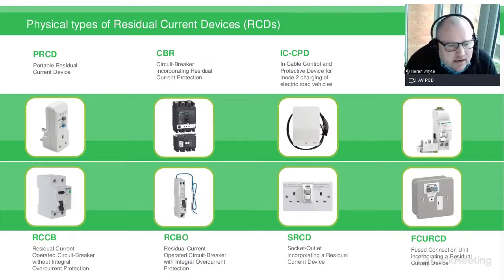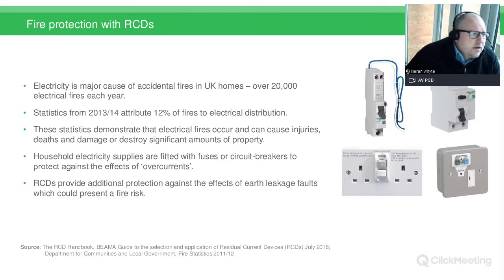They were probably seen in toilet areas, commercial and public toilet areas, where they used to feed the hand dryers, and they'd just be mounted at high level out of reach, which gives protection then to the cable and the circuit going down to the actual hand dryer itself. Not seen much these days. What we're seeing more is at point of source, the RCBO controlling the whole circuit, because there are very few exclusions now where you get away without fitting it. So on to the next page.